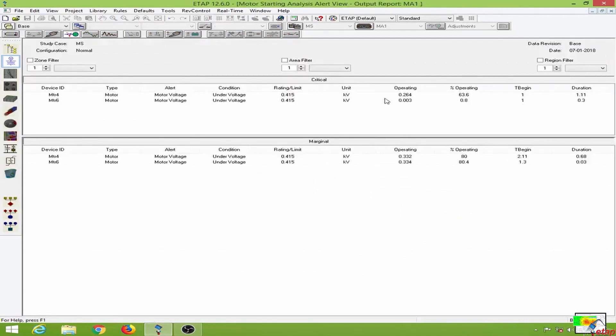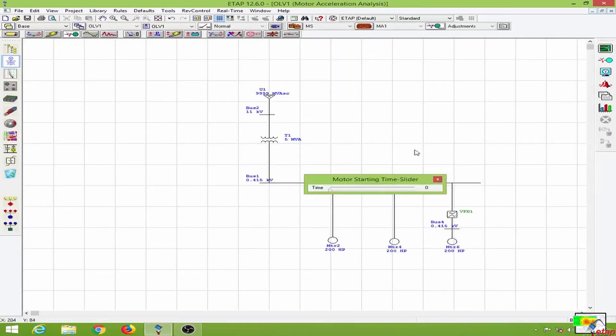We will neglect these warnings because this system is only for demonstration purposes. In an actual system we do not start all the motors at once. The problem shown here is that the motor voltage is becoming under-voltage for a period — motor 4 is under voltage for 1.1 seconds and motor 6 is under voltage for 0.3 seconds and so on.